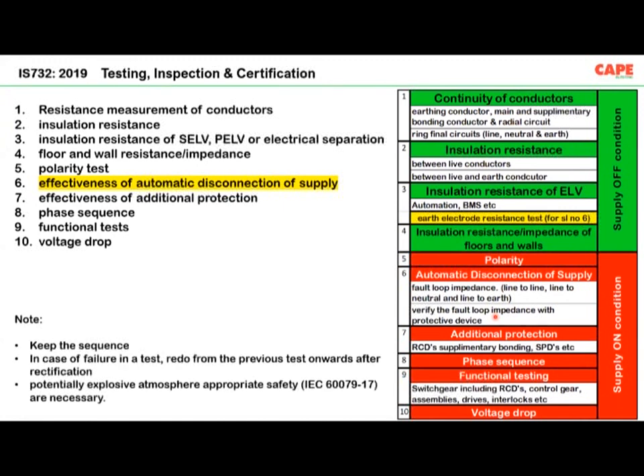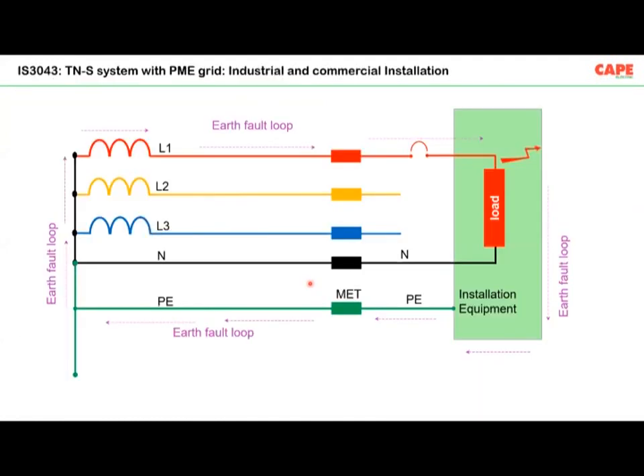Now, there are several conditions. I am only showing the testing of the installation, but don't think that testing will completely solve your problem. No. The standard is advocating for an inspection. Approximately 16 parameters must be inspected, and these 10 tests must be carried out in order to ensure safety. Out of this, there are 2 tests related to earthing: number 1, resistance measurement of conductors, and number 6, effectiveness of automatic disconnection of supply. I will show you from the standards later on.